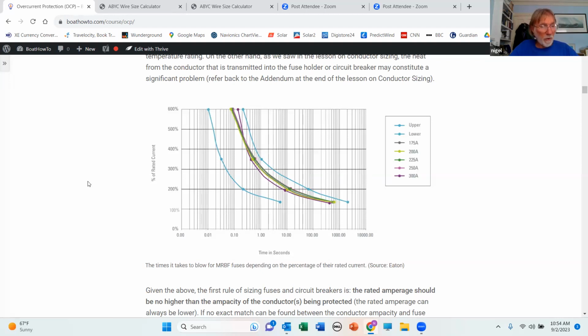So the standards don't require a fuse in that circuit. However, if we get a short circuit in the starter motor, we're going to start a fire. And we've had a number of fires on boats because of that. So I always put a fuse in that circuit.